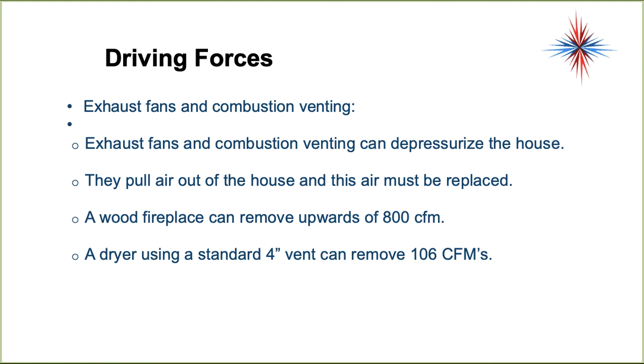Exhaust fans and combustion venting cause pressure changes — they suck air out of a building and can depressurize the house. A wood fireplace can remove upwards of 800 CFM. A dryer using a standard four-inch vent can remove 106 CFM of air. That's a lot of air, and a dryer runs for usually over an hour, so you have to be aware of how long you're running these appliances.